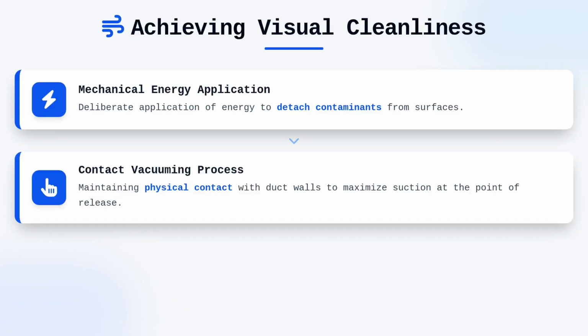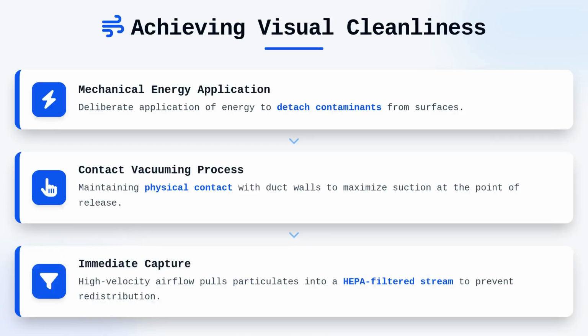When we discuss contact vacuuming, we are describing a process where the vacuum nozzle or attachment maintains physical contact with the duct wall or component surface to maximize suction at the point of release. To perform this correctly, you must select the appropriate attachment for the specific material you are addressing, such as utilizing soft bristled brushes for delicate components or rigid plastic nozzles for heavy debris on non-porous sheet metal.